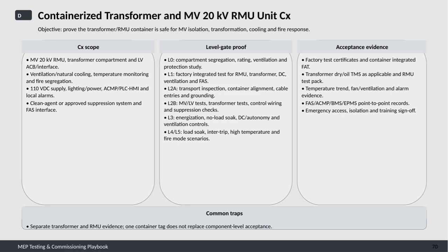It covers the medium voltage RMU, the transformer compartment, and the low voltage air circuit breakers and interfaces. It includes ventilation and natural cooling systems, temperature monitoring, and fire segregation. The electrical supply systems at 110 VDC, lighting, power controls including the air circuit breaker management platform, and local alarms are also within scope. Furthermore, fire suppression systems like clean agent or other approved methods, along with their interface to the fire alarm system, are essential components of the commissioning.